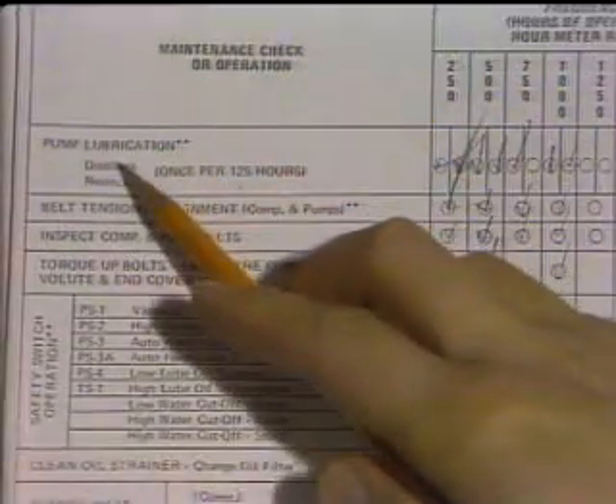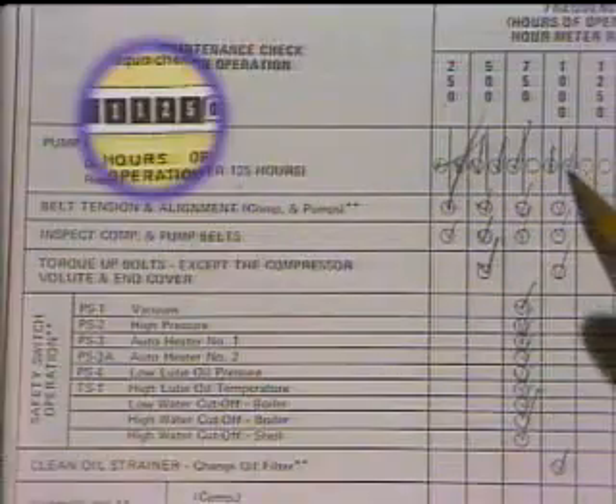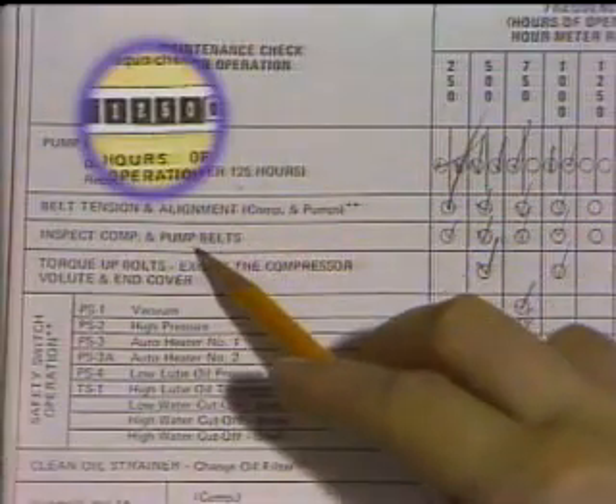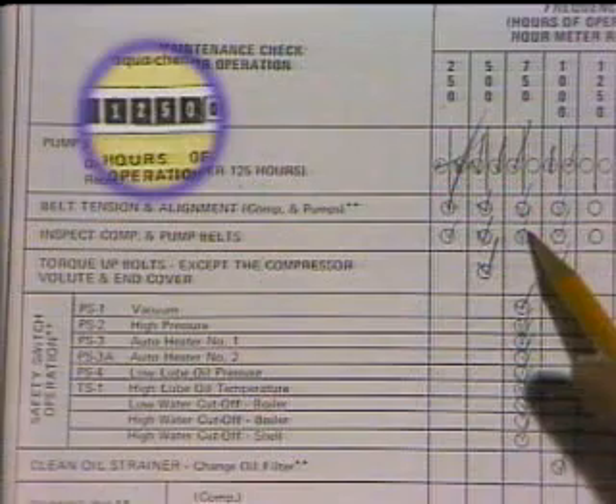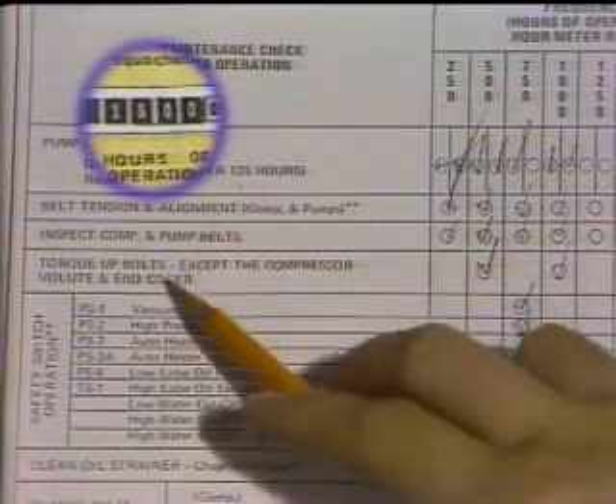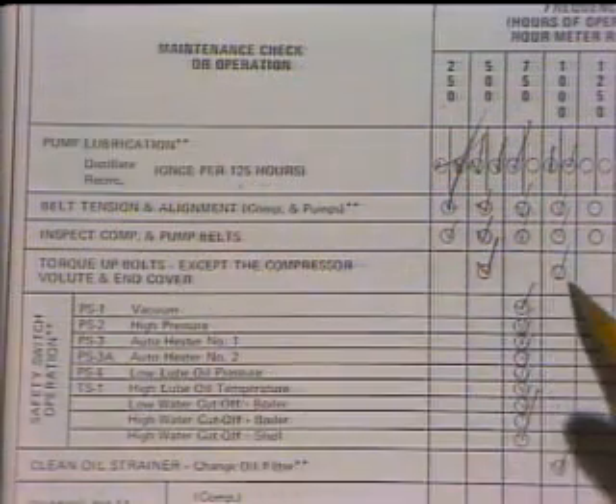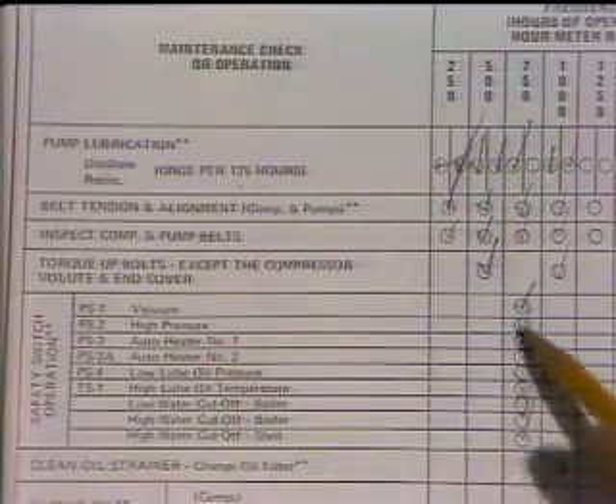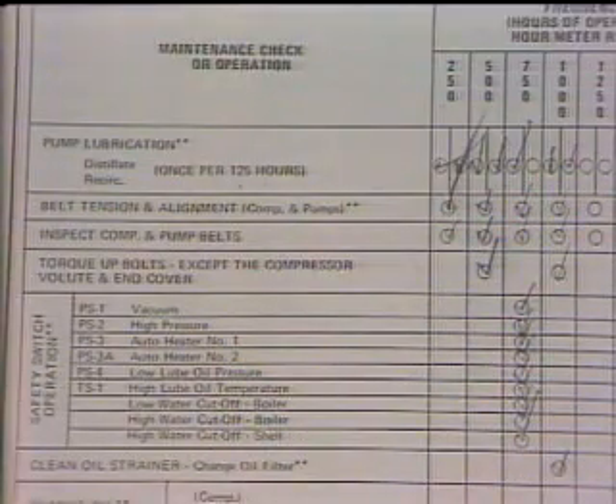Pump lubrication needs to be checked every 125 hours. Belt tension and alignment and belt inspections at 250-hour intervals. Bolt torque checks at 500-hour intervals. And safety switch checks at 750-hour intervals.